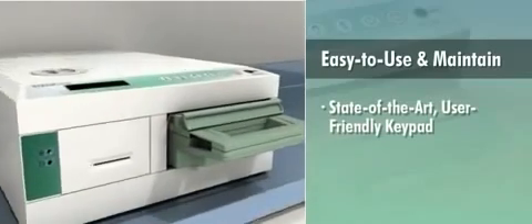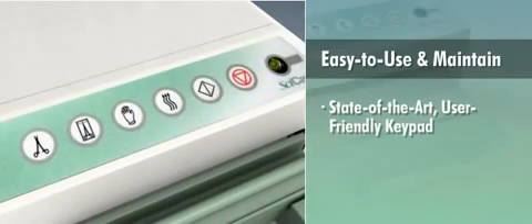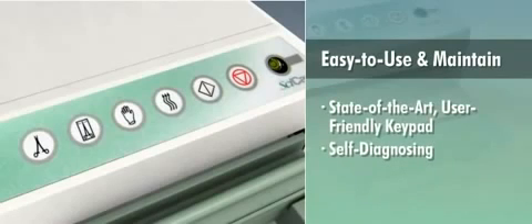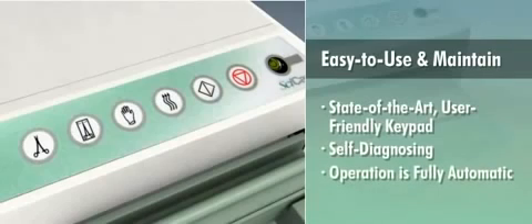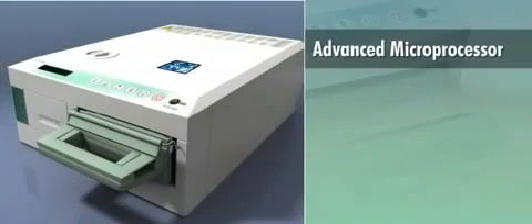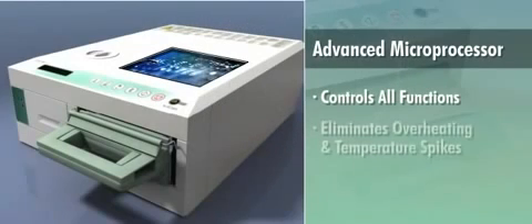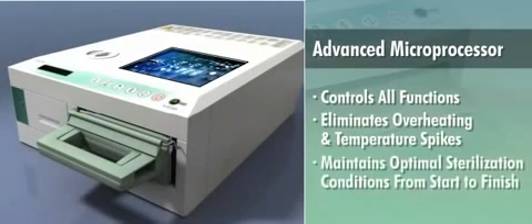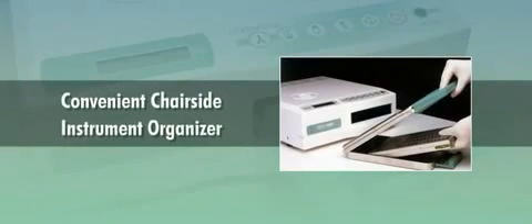A state-of-the-art, user-friendly keypad displaying clear prompts makes STATIM easy to use and maintain. It is self-diagnosing, so if a problem occurs, it will be indicated on the electronic display. STATIM's operation is fully automatic. Simply select one of 3 programs and begin the cycle with a touch of the keypad. Its advanced microprocessor controls all functions, eliminating overheating and temperature spikes, maintaining optimal sterilization conditions from start to finish. When sterilization is complete, the dental staff can work directly from the STATIM cassette tray as a convenient chairside instrument organizer.